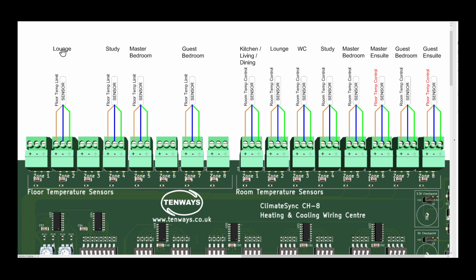Here we can see that in the lounge we require a floor sensor, in the study, in the master bedroom, in the guest bedroom. These rooms require a floor sensor for floor limit protection. The sensor should be installed touching the flooring, under the flooring. Best to keep it away a bit from the heat source, so we sense the temperature under the floor, under the wooden floor, and not sensing the temperature of the pipes, and then it will stop too early.